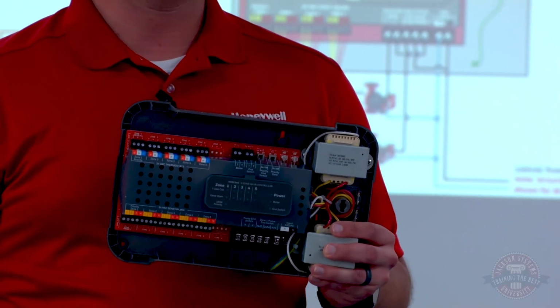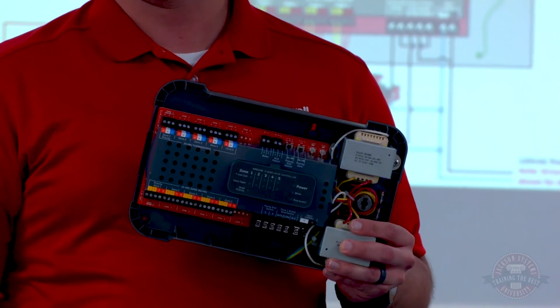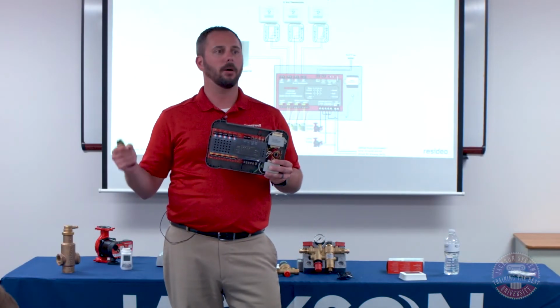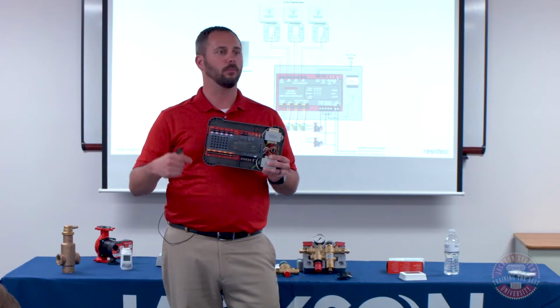The other thing that we've seen is there's more and more people using modulating and condensing boilers. With mod/con boilers, most of them have the pumps wired directly into the boiler itself.